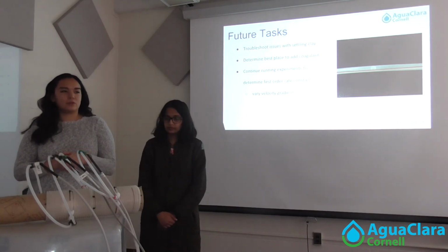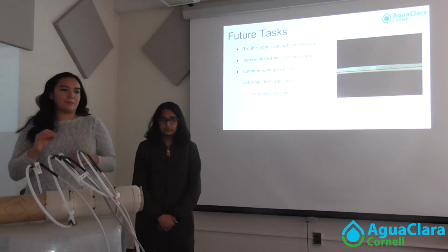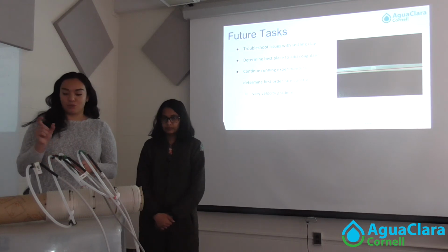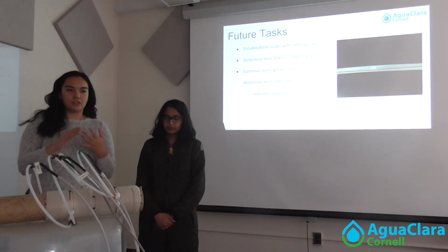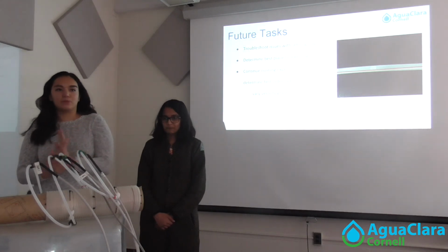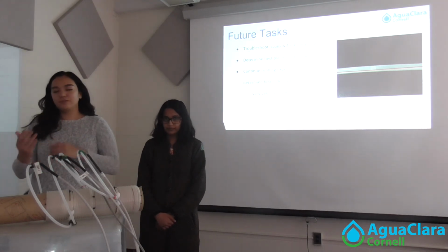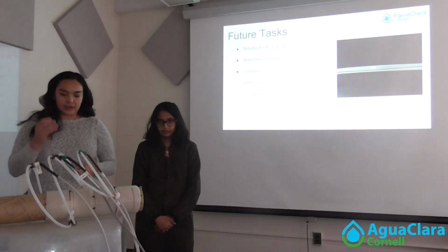Another thing is we kind of want to determine what is the best place to add coagulant. Right now we're adding it right before the flocculator, but perhaps it'll be better to add it a little bit before that so the clay and coagulant can interact a little bit more before entering the flocculator. Future teams will have to sort of experiment with that.